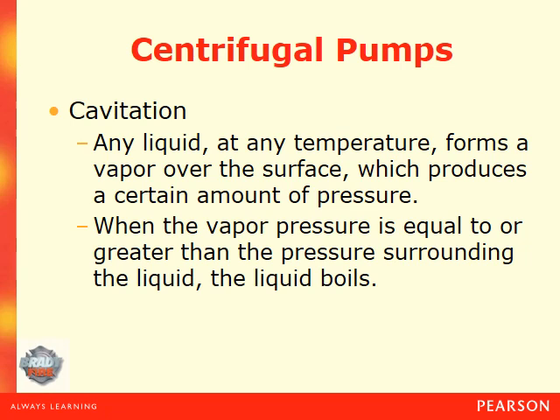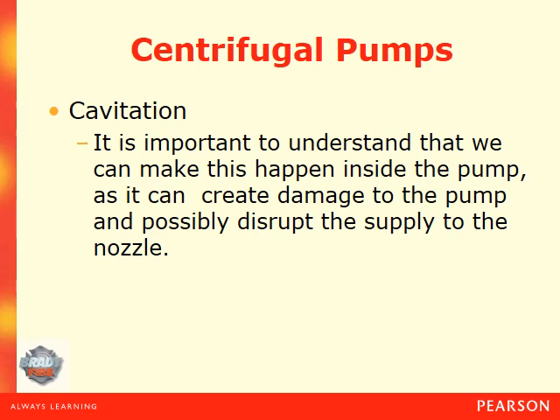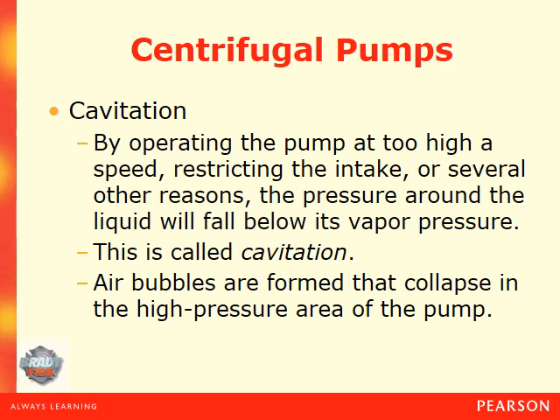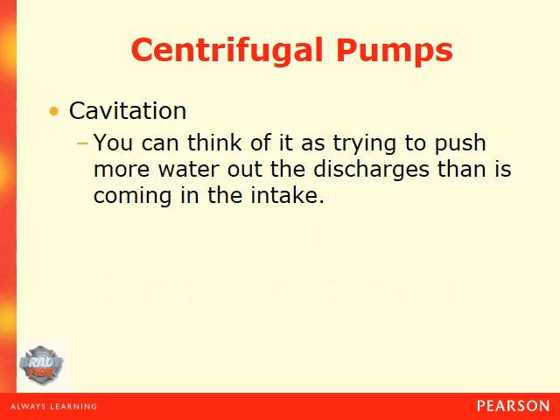Cavitation: any liquid at any temperature forms a vapor over the surface which produces a certain amount of pressure. When the vapor pressure is equal to or greater than the pressure surrounding the liquid, the liquid will boil. By operating the pump at too high a speed, restricting the intake, or several other reasons, the pressure around the liquid will fall below its vapor pressure — this is called cavitation. Air bubbles are formed that collapse in the high pressure area of the pump. You can think of it as trying to push more water out of the discharge than is coming in the intake.